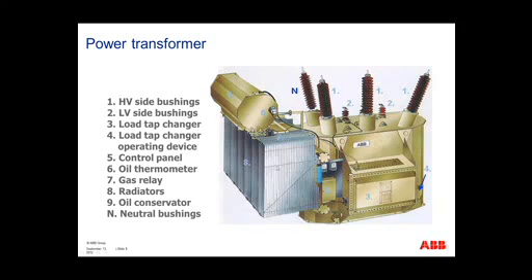Associated with oil, you have an apparatus labeled as number 8. This is going to be your radiators. This is what circulates the oil around the transformer and helps cool the oil. You have an oil reservoir that sits on top of the radiator. Other possible cooling mechanisms could be fans connected to this radiator to help cool the oil, to help keep the core at its operating temperature.